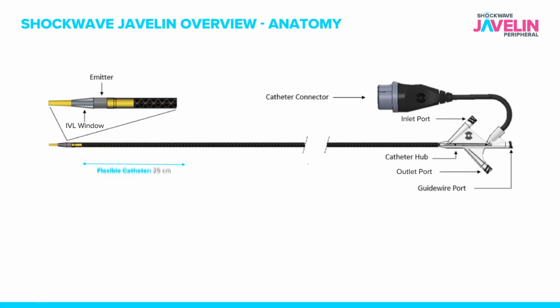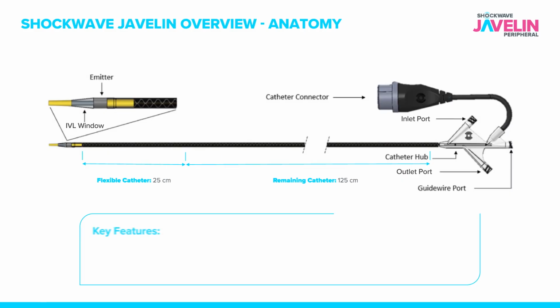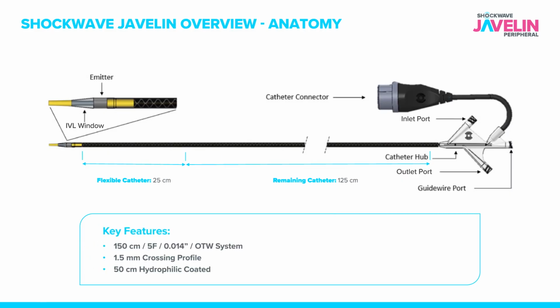Here's the anatomy of the catheter. You can see it's a 150 centimeter shaft, a 0.014 platform. It's an over-the-wire system. The crossing profile is 1.5 millimeters. The distal 50 centimeters of the shaft is hydrophilic, and the distal 25 centimeters is flexible. This device has 120 pulses, 12 cycles of 10 pulses each, with a 10-second break between cycles. You can see the distal window.